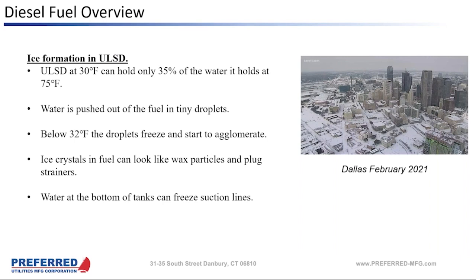That could be all water. So the water gets pushed out of the fuel in little droplets, and if the fuel's below 32 degrees F, the droplets freeze and start to agglomerate. Ice crystals in the fuel can look just like wax particles and plug strainers too. And then if the water drops out completely, the water at the bottom of the tanks can freeze suction lines.